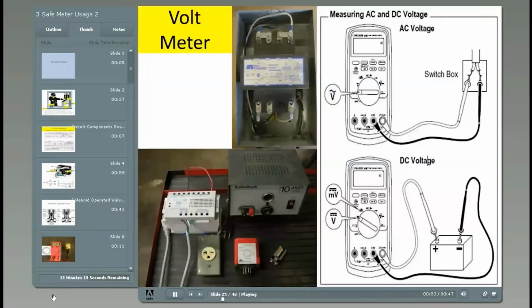Voltage. The voltmeter selector switch is set for AC volts, and the voltmeter test leads are connected across 2 points of potential difference. This is an auto-ranging meter, and the value should read 120, and the engineering units displayed should be volts AC. It is important to focus on reading the engineering units since the meter is auto-ranging and may be reading a mere 120 mV.